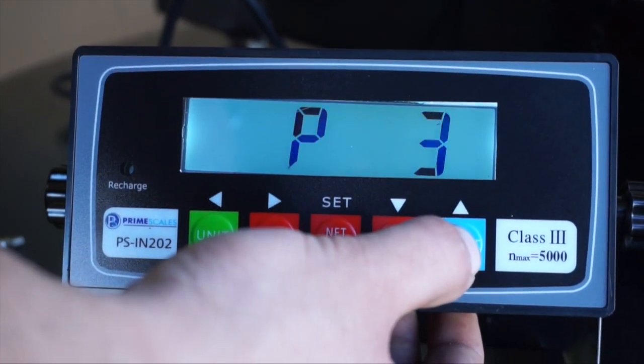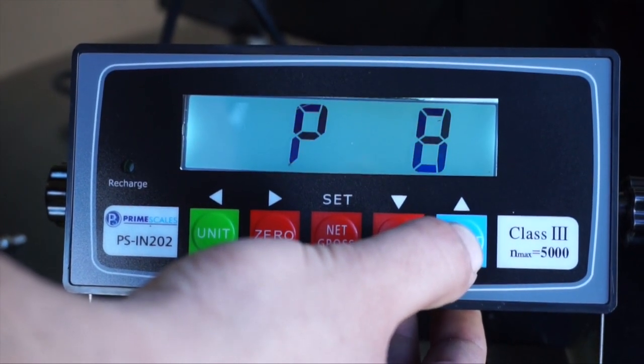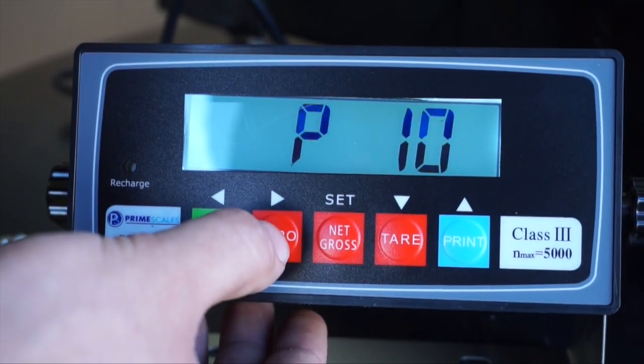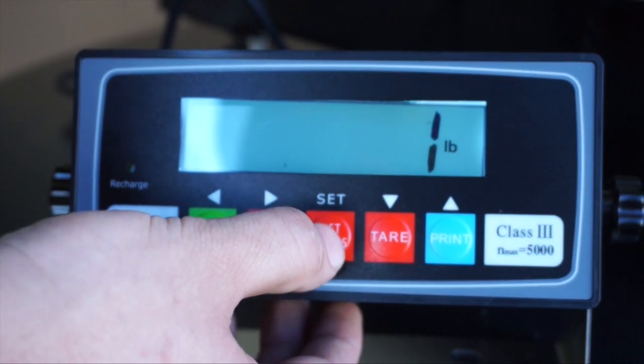Press the print button till you move up to the P10 or parameter 10. Press zero to enter. P10 sets scale to read in pounds or kilograms when turned on. Although you can switch unit anytime during weighing. Choose one for pound or two for kilogram and save setting by pressing net gross.